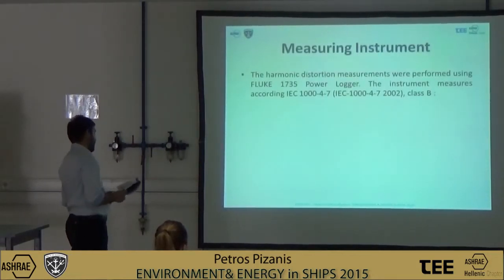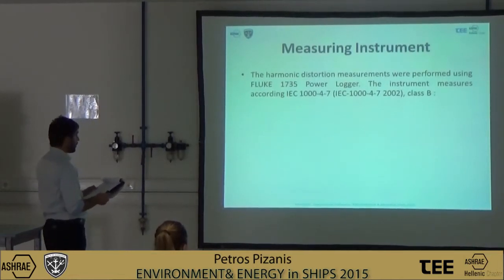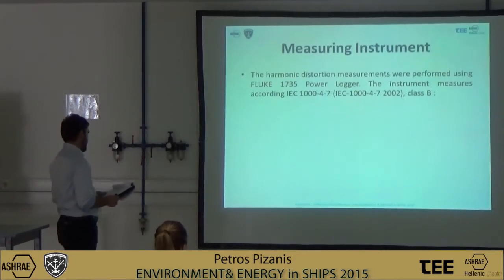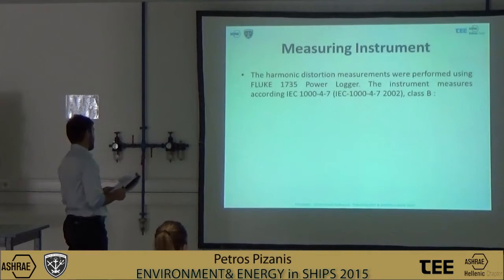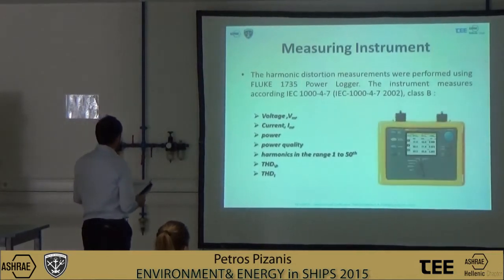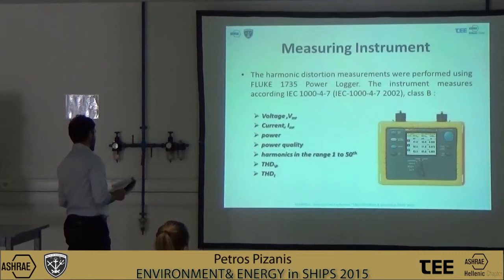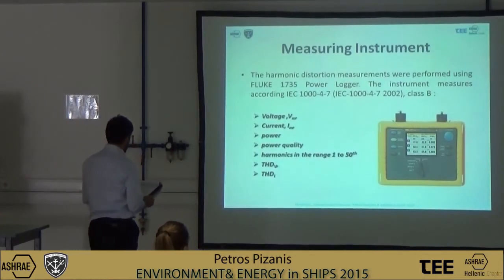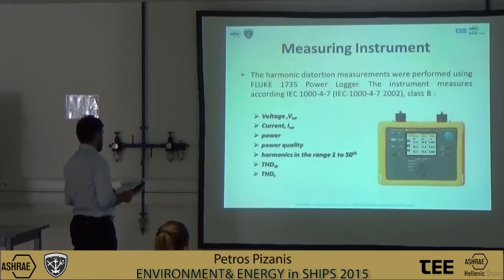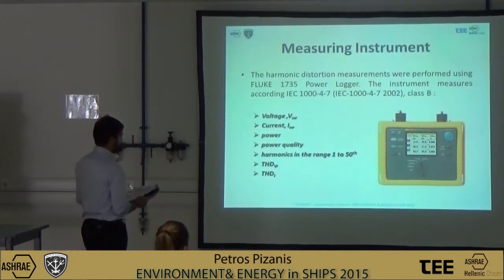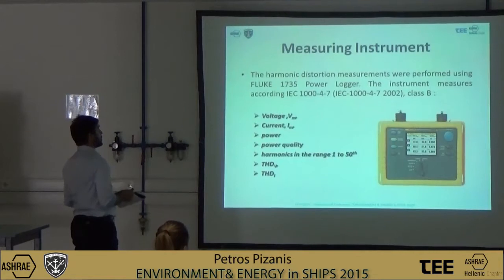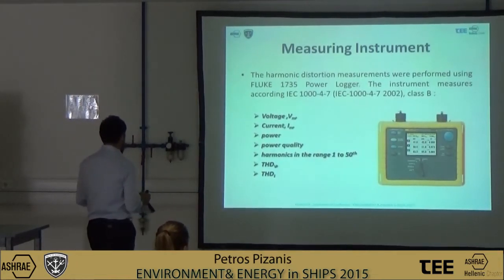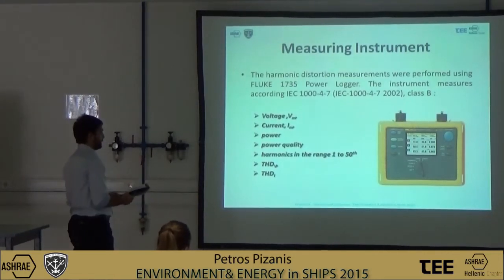Those reasons lead us to investigate whether distortions are present in our working environment and also whether they can be rectified. For this to be achieved, we must study and record, so we could be prepared for the appropriate prevention system. The recording device which shall be used is the Fluke 1735, which is a logger that records harmonics data with large accuracy and always in accordance with the IEC and European legislation. The record we got helped us to find and create an improved solution to exclude these factors. The meter allows us to find volts and currents, their peaks and limits, and harmonic distortions from the first until the 50th harmonic.